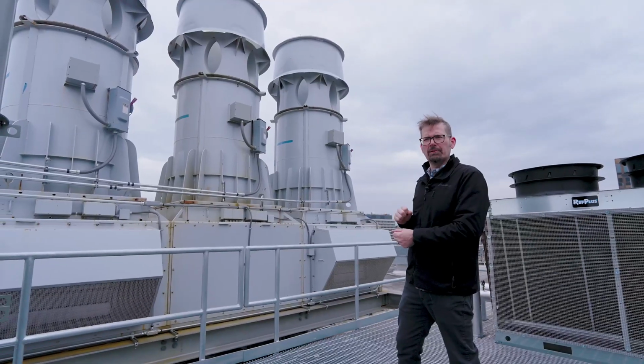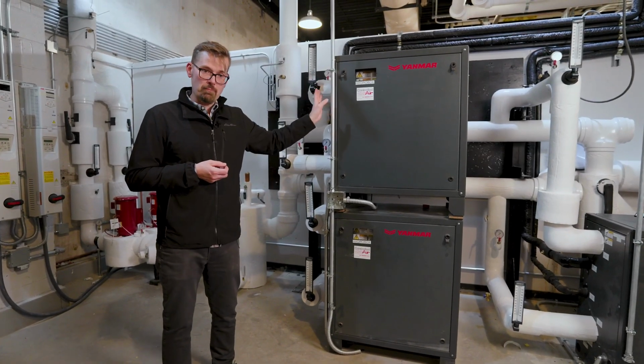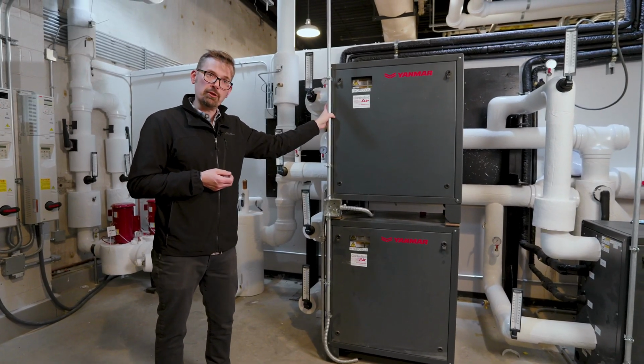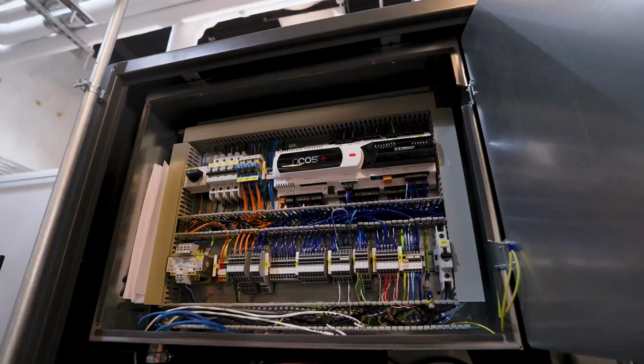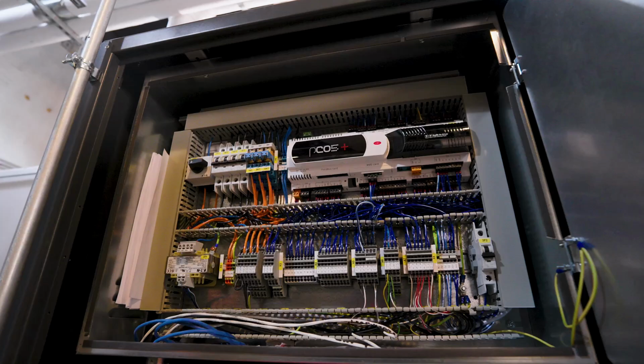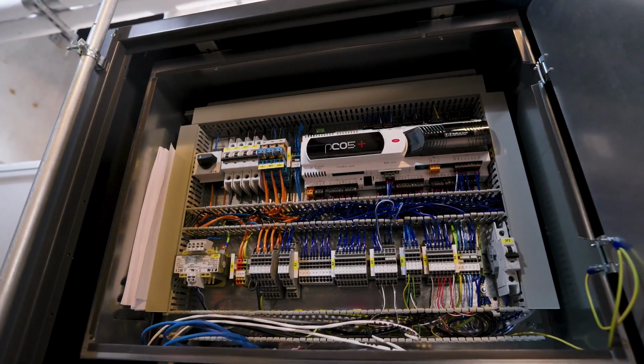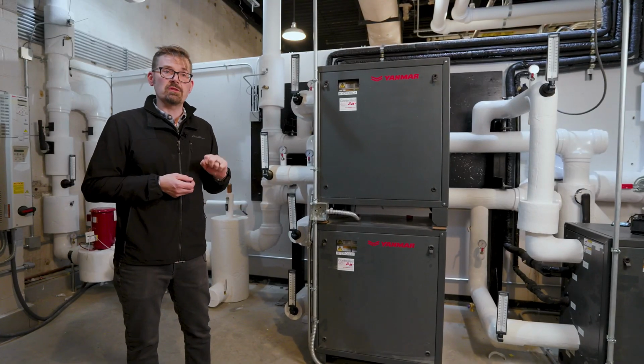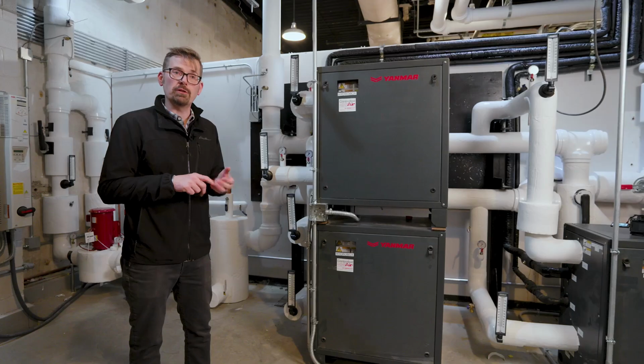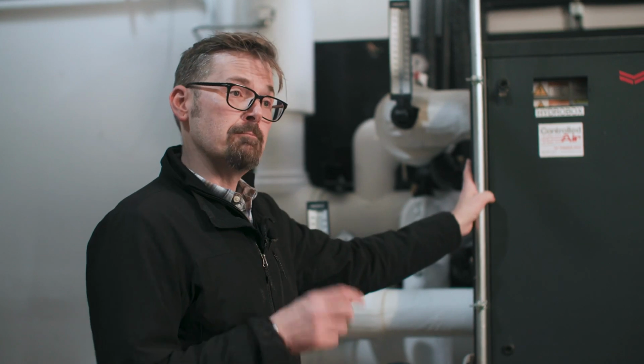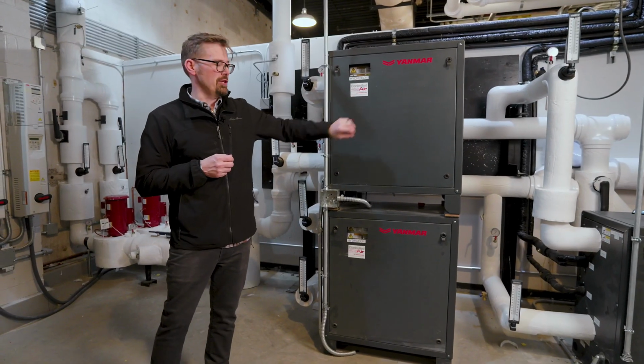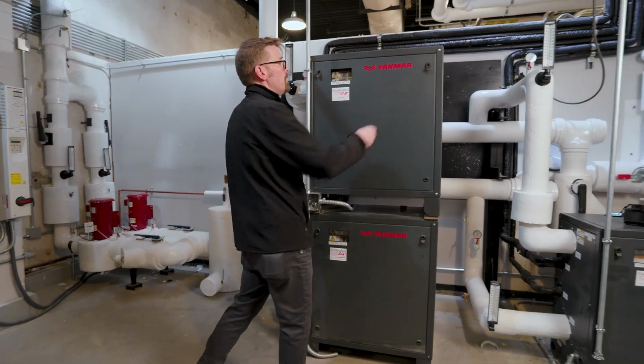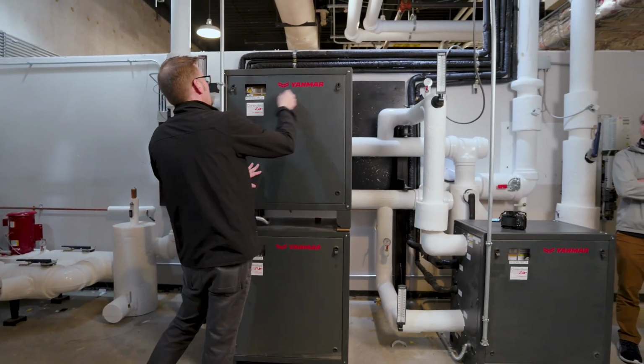We decided to go with the Yanmar Hydrobox application, which allows us to use a GHP that is paired with this Hydrobox, which will allow you to either create hot water or cold water with the system. So either you could do heating or cooling with it. In this application, we were looking for cooling. So we are making this a strictly chiller-based operation for these Hydroboxes. There's a heat exchanger in here and also a smart pump within this.